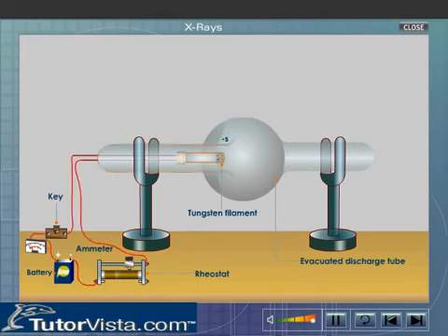There is a hollow molybdenum cylinder surrounding the filament. This cylinder, which is referred to as cylindrical shield, is maintained at a negative potential so that it focuses the electrons emitted by the filament onto the anode.